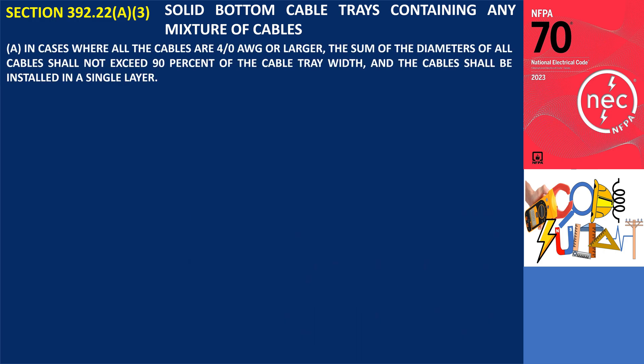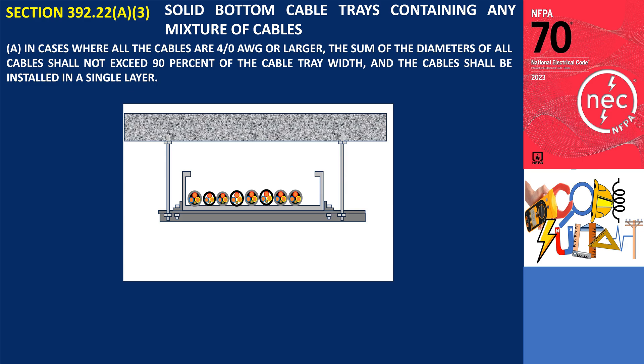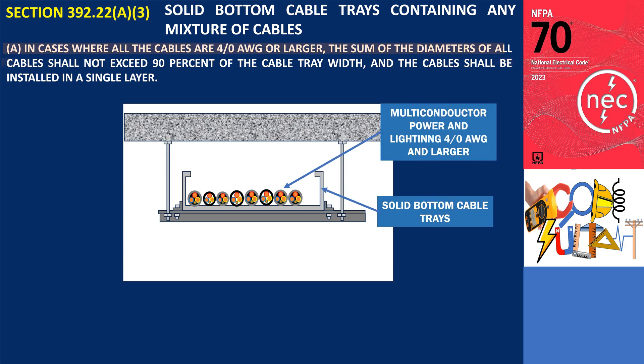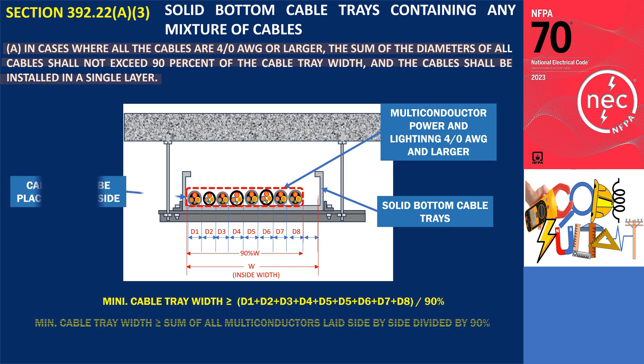Section 392.22(A)(3)(a) states that in cases where all the cables are 4-aught AWG or larger, the sum of the diameters of all cables shall not exceed 90% of the cable tray width, and the cables shall be installed in a single layer.